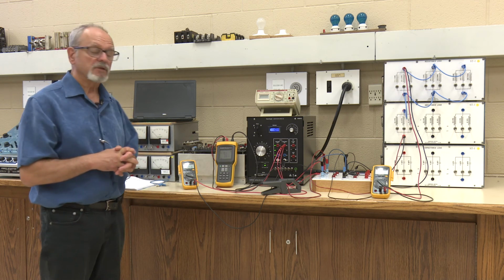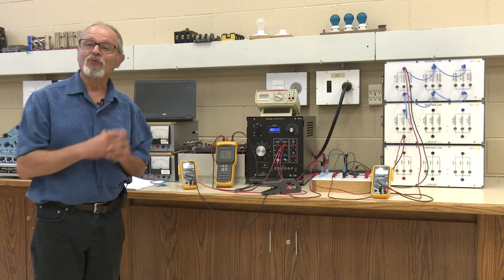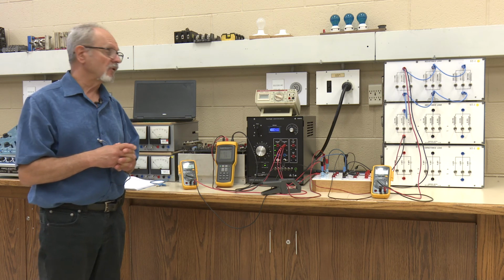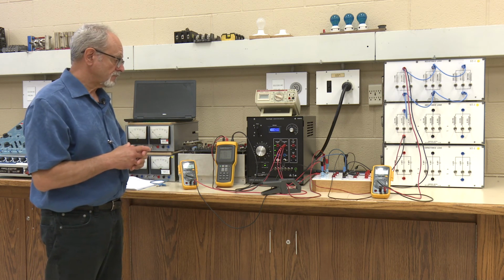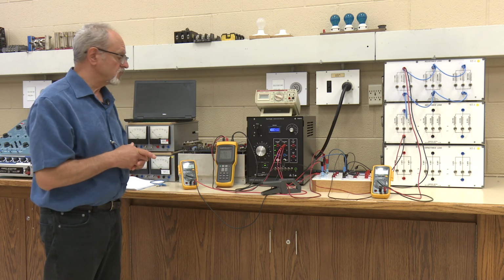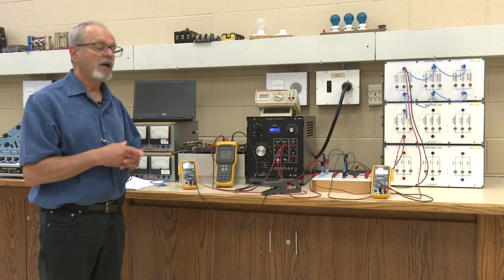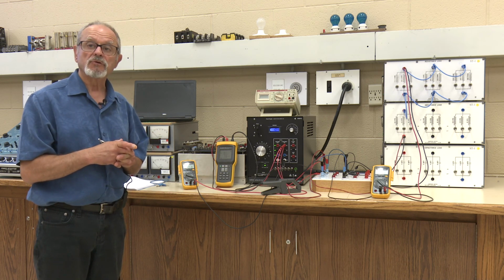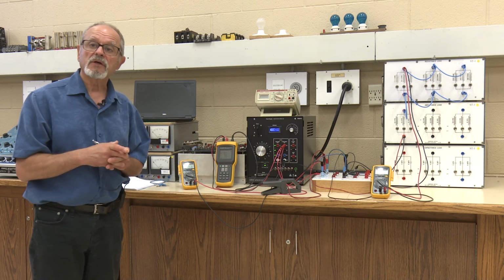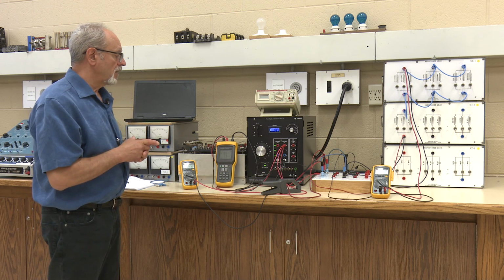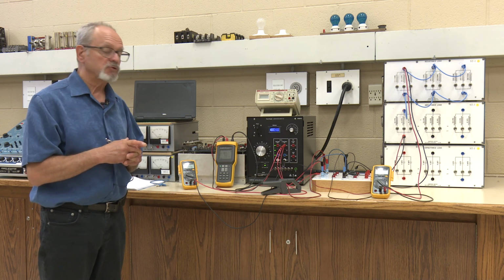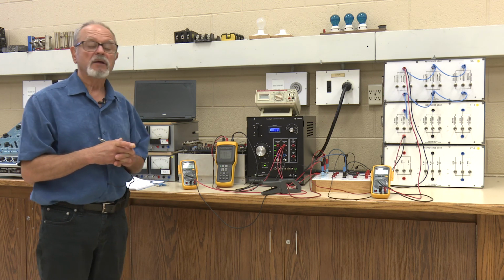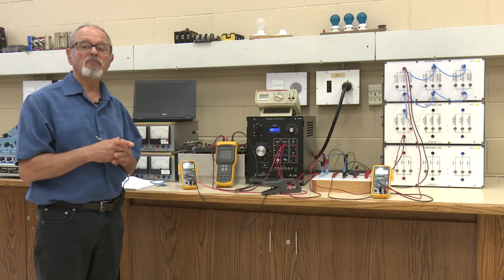And the reason it's such a concern is because if we have, say, one rogue customer, if you will, who is generating a lot of harmonics because they actually have a lot of switching loads in their plant, they will be the source of the distortion at the substation. And if we exceed or develop a lot of distortion on the voltage waveform, it will affect the other customers quite possibly. So it behooves that customer who's generating those harmonics to do something about it. And we call that a mitigation technique, which we'll study in lab 5 and 6.